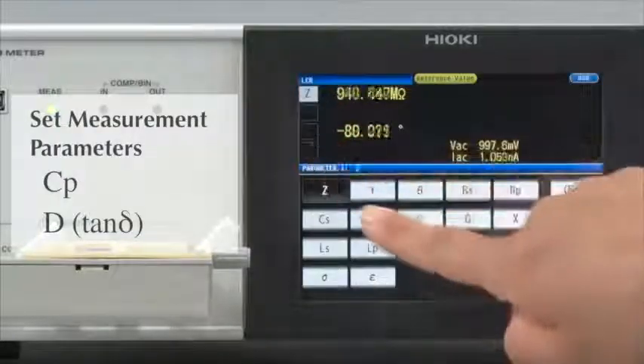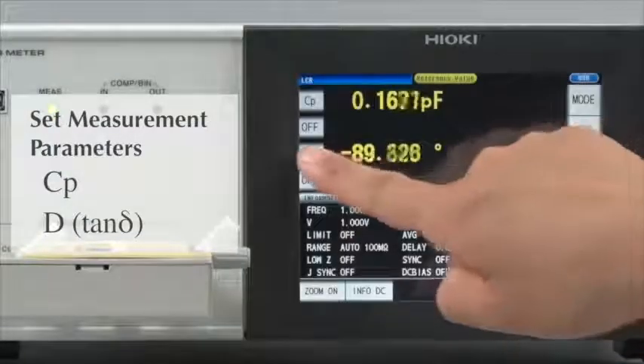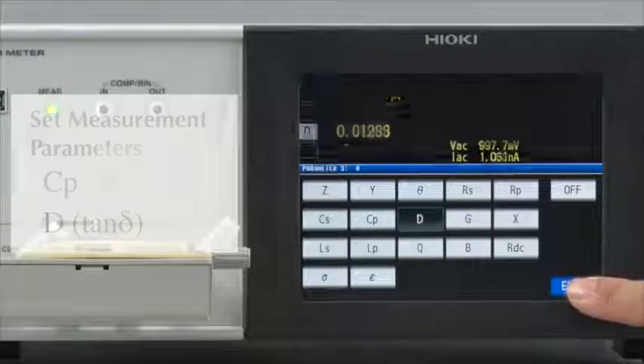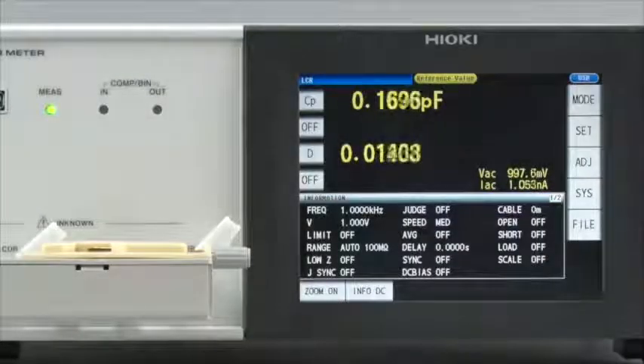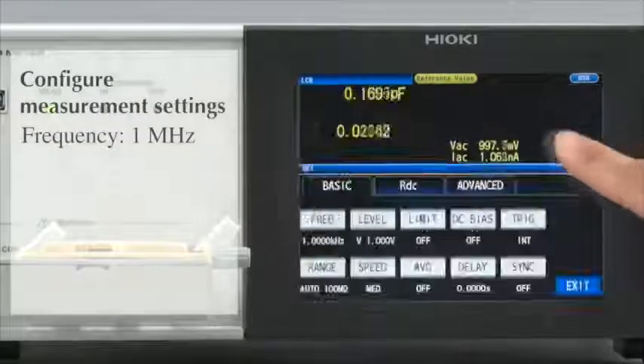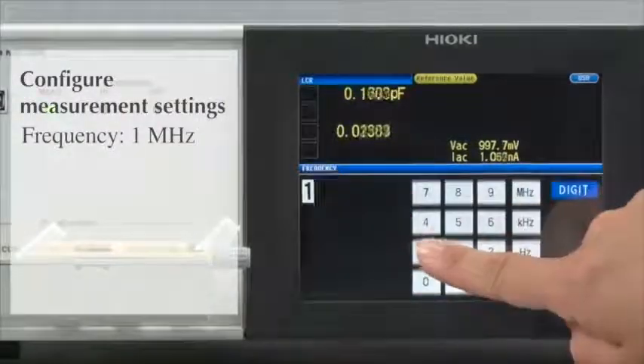First, select C, P, and D. Now, configure the measurement conditions. Set the measurement frequency at 1 MHz.